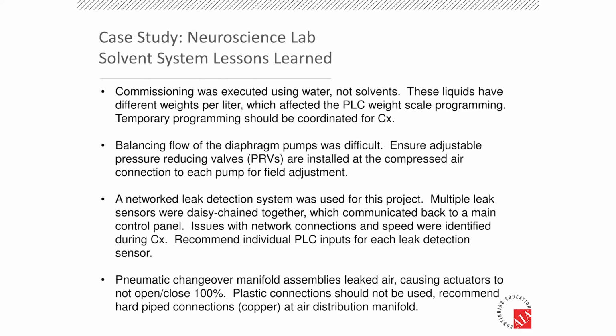Another thing, we had a networked leak detection system where every sensor out in the field had a comm wire to it and communicated kind of MSTP across the chain. We had a lot of issues with those sensors, and I would highly recommend that you use individual inputs instead of a networked system. There were issues with lag time as it related to actually detecting water. We also had a lot of issues with the setup and testing of the system.